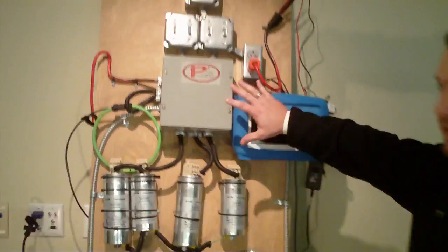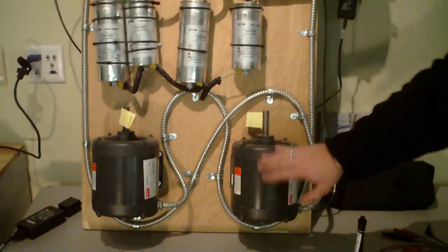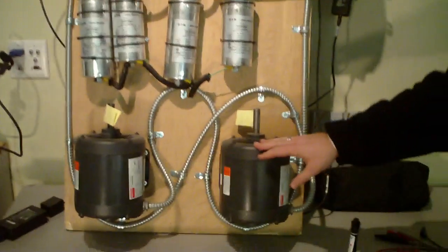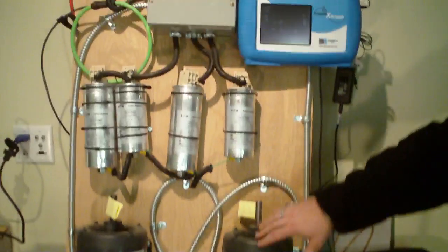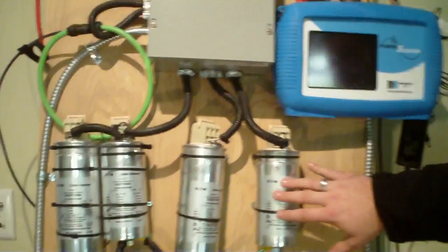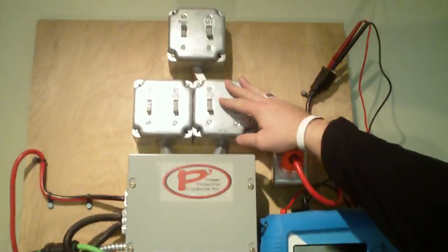And now I'd like to show you in a live demonstration how this works. Up here on this board, what we have here is two inductive motors, similar to what you might see in an industrial application. And above those on this board are different capacitors of different kVAR values, also tied to switches that we can manually operate through this live demonstration.